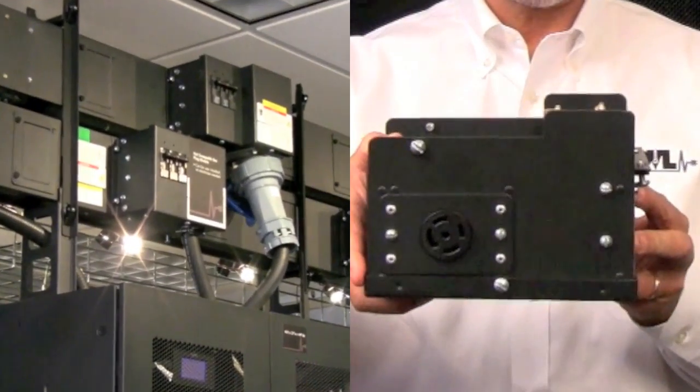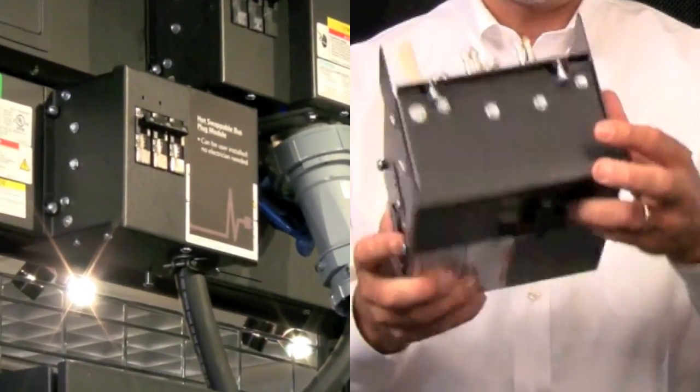First, less clutter, reduced obstruction to airflow in raised floor environments, reduced capital cost and total cost of ownership. Ease of field changes, in other words, electricians aren't needed to either change rack PDUs or even to change receptacles through bus plugs, as I'm showing here in my hands. Last of all, this simplifies the wiring methods in the data center.